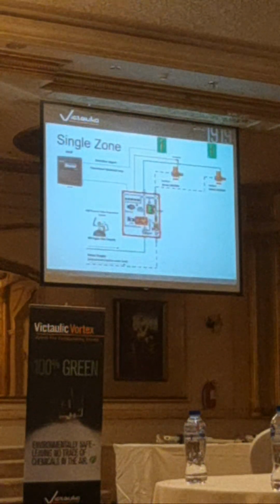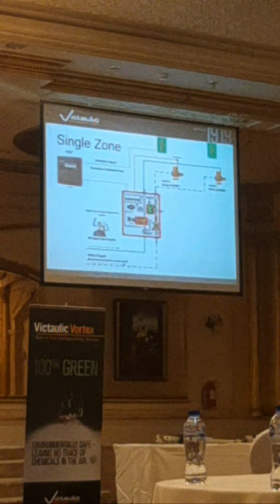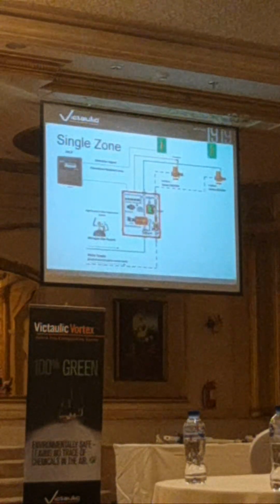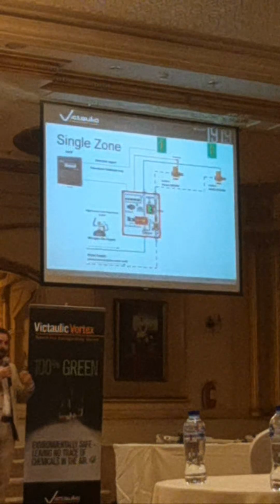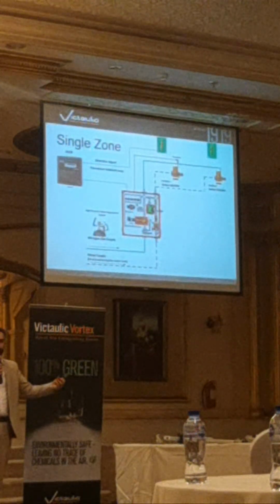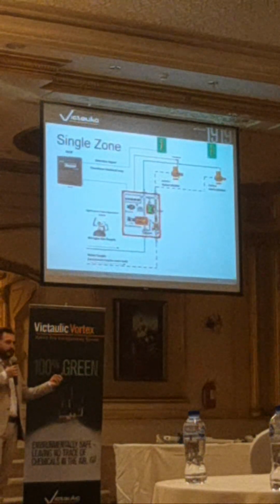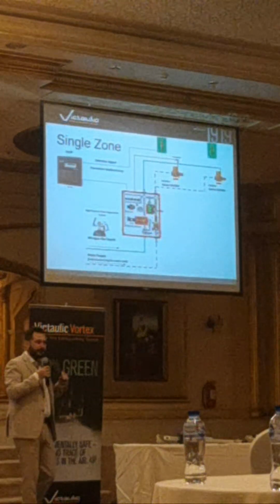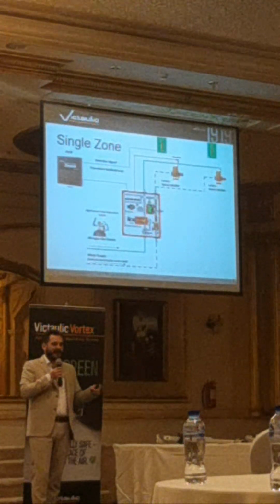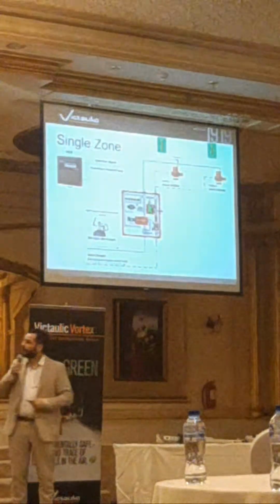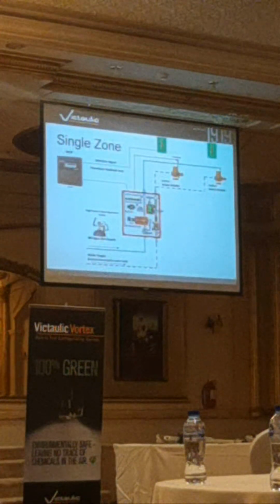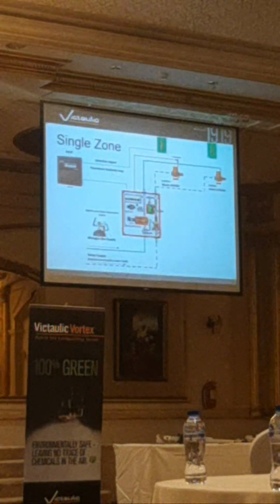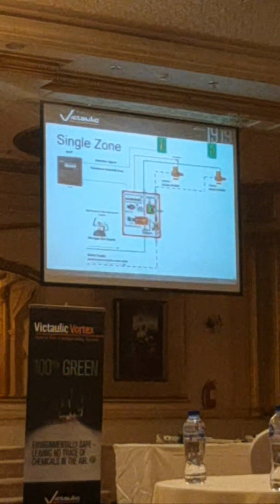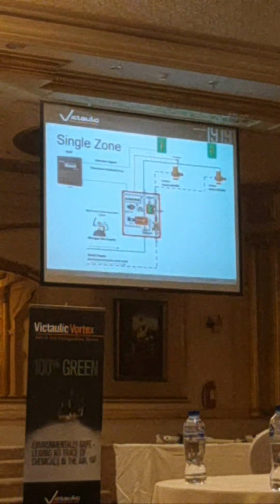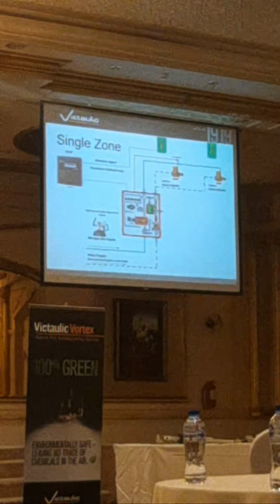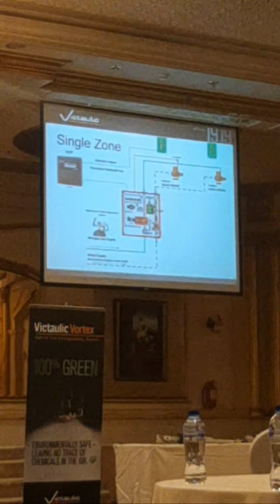nitrogen is gone. I haven't talked about the water yet because the water comes after the nitrogen. We don't want to have the water first because otherwise you don't have the nitrogen pressure to break down those droplets to the small size. So first nitrogen. Once we know that the nitrogen pressure is high enough, the ball valve, the green one inside of the panel, is going to open up, allowing the water to go, and then the two combine, they do the hybrid mist for the duration of the discharge, which is going to be less than 3 minutes.